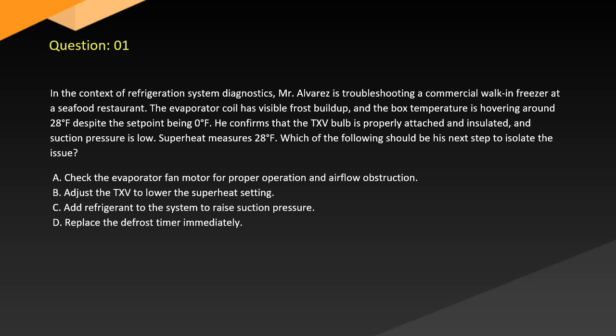Question 1. In the context of refrigeration system diagnostics, Mr. Alvarez is troubleshooting a commercial walk-in freezer at a seafood restaurant. The evaporator coil has visible frost buildup and the box temperature is hovering around 28 degrees despite the set point being 0 degrees. He confirms that the TXV bulb is properly attached and insulated and suction pressure is low. Superheat measures 28 degrees. Which of the following should be his next step?